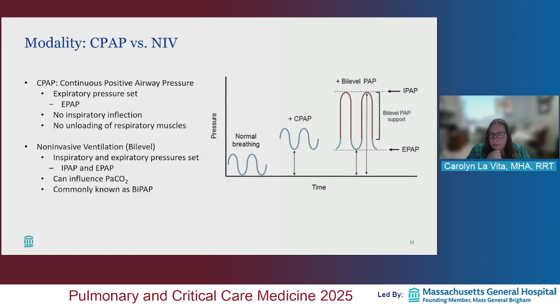We'll talk about this a little bit later, but some of the technical considerations with this is you have to understand which device you're using. Some of the ICU ventilators, when you're setting BiPAP, you're actually setting the CPAP level or the EPAP level plus the driving pressure. Some of the home devices that are used, you're setting the EPAP or CPAP level, but in fact, you set the inspiratory pressure, the PIP, and not the driving pressure. You can see that if there's confusion or miscommunication about that, the ventilatory support that the patient's getting is offset by the level of PEEP that is applied.